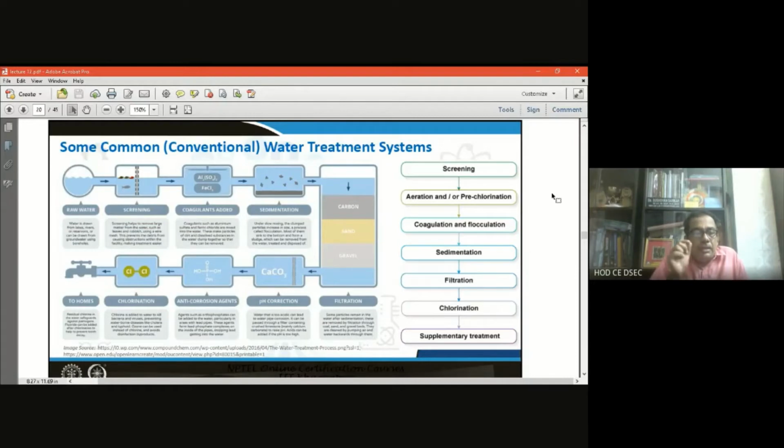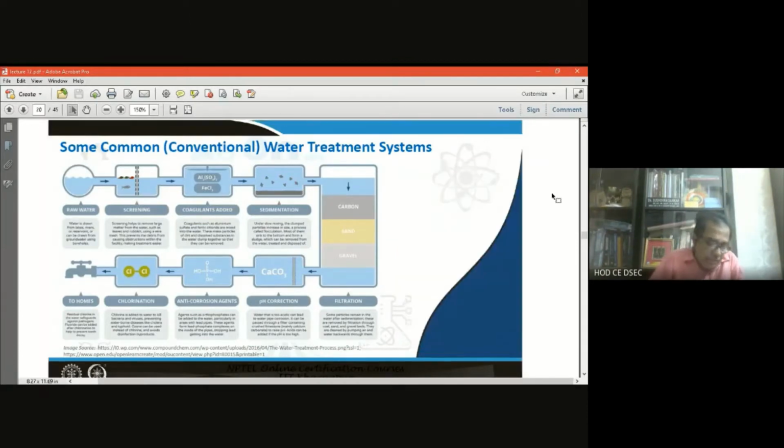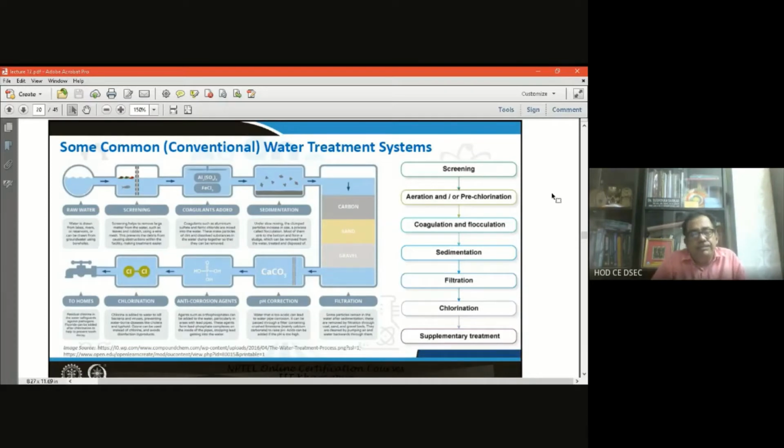And after the disinfection, some residual amount of chlorine, like 0.2 milligram per liter, has to be maintained, because after the disinfection, when we send the water into the distribution pipeline to the end user system, through this conveying pipe network, the water may be contaminated. There may be a chance of contamination of the water over the long travel distance through the pipes. So that's why we maintain the minimum chlorine residual of 0.2 milligram per liter even after the chlorination, that is, the disinfection done for distribution purposes. That has to be clearly kept in mind.